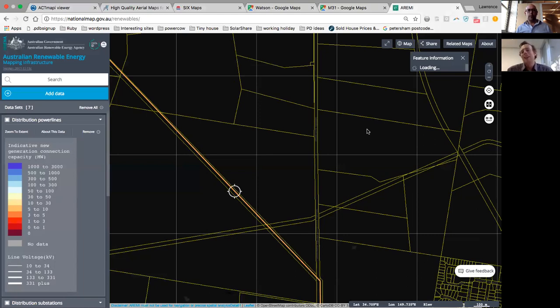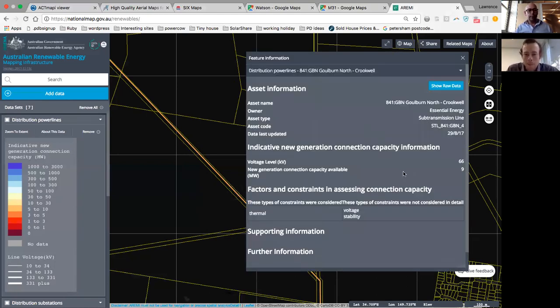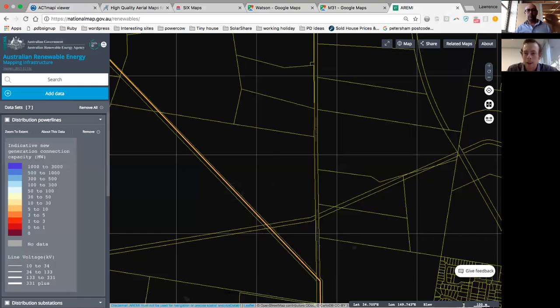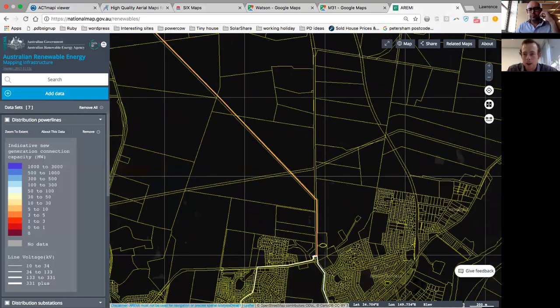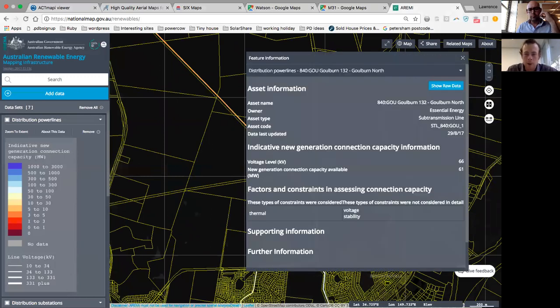You can start to gauge a little around this: a 66 kV line isn't likely to have much more than a certain capacity. One very basic rule of thumb is that you might expect a little more than the voltage value as your available connection capacity in megawatts — a very quick and dirty rule of thumb. Many sites break this, and many are much more constrained, but a 66 kV area able to accept hundreds of megawatts would surprise me.